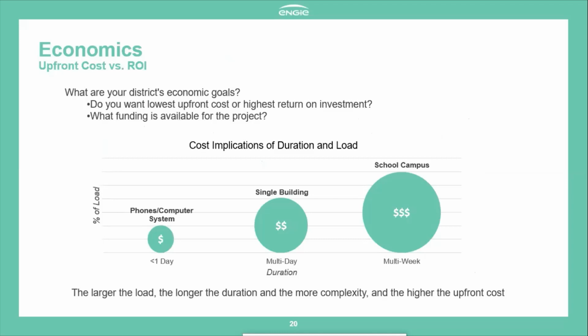What we're typically seeing on most facilities is we're using about 50% of the batteries as backup power, and the other 50% to do peak demand shaving or arbitrage or other utility services to make the project look more financially attractive. Many of the funding sources we get here in California, like the California SGIP, cannot be 100% dedicated to backup power, because we have to cycle and discharge the batteries as part of the incentive. So we do multiple services with that, which improves the financial ROI.